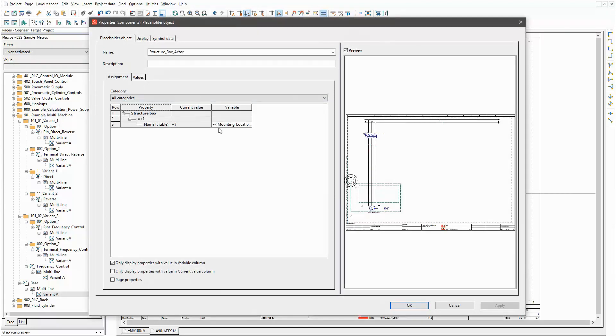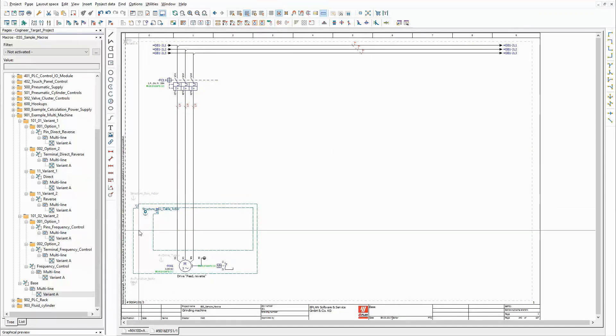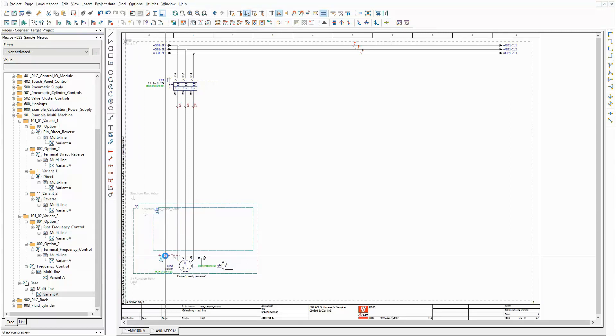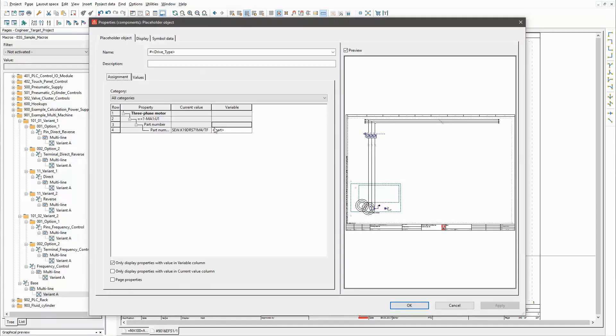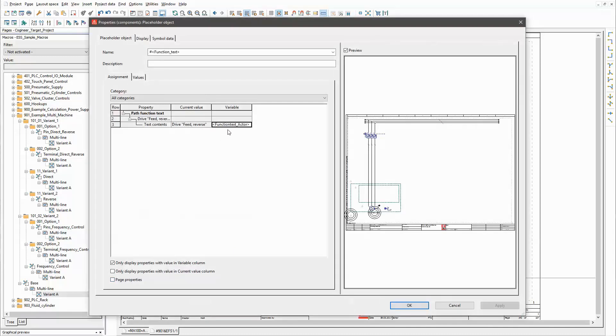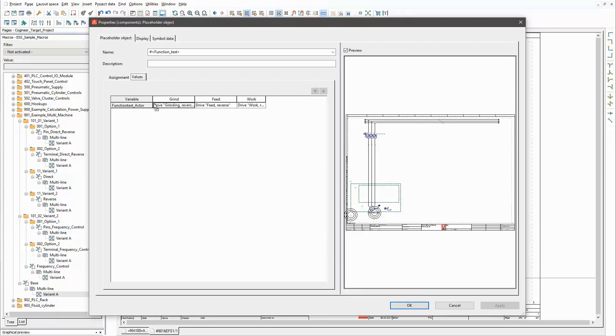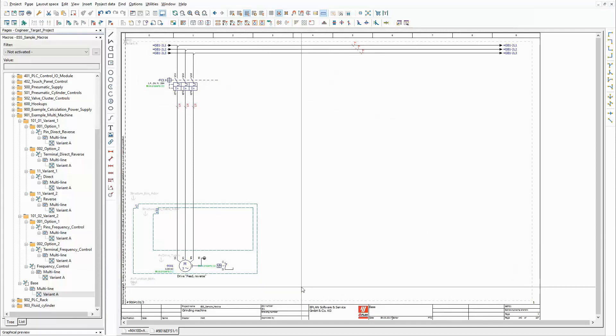In addition there are several placeholder objects. This one contains a single variable that is referenced to the mounting location of the structure box. The next one is similar — it is referenced to the mounting location of the second structure box. The third placeholder object is referenced to the drive type and contains two value sets. They contain part numbers for motors with different power outputs. And the last placeholder object contains a value set that is used for the function text that is displayed below the drive. Depending on the selected options in the project builder, the partial circuit for the drive is assembled out of these macros.